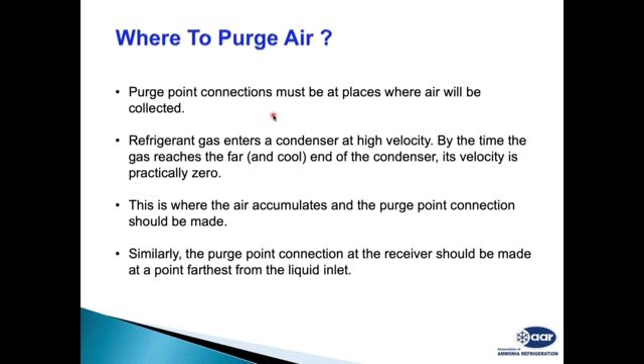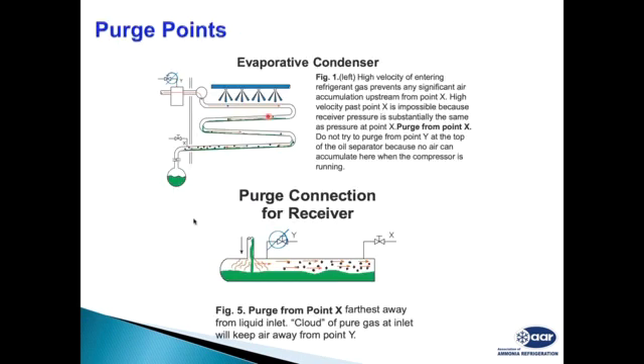The receiver is the same thing. It has to be the furthest point from the liquid entry to the condenser, because when liquid is entering the condenser, it is possible that ammonia gases will be close to the purge entry point. So we have to take this at the end. You can see we cannot purge air from the inlet of the evaporative condenser or the condenser inlet. We can purge it from the outlet.